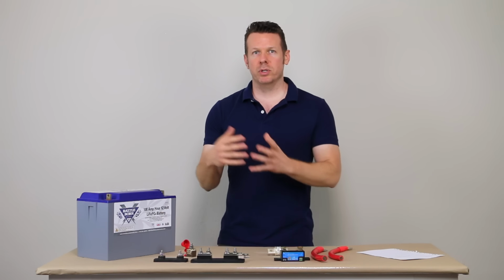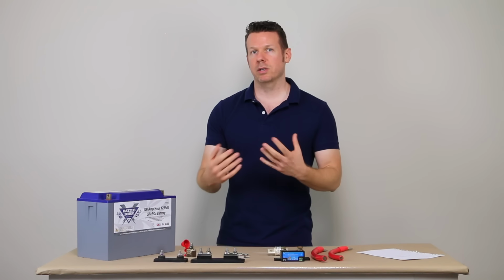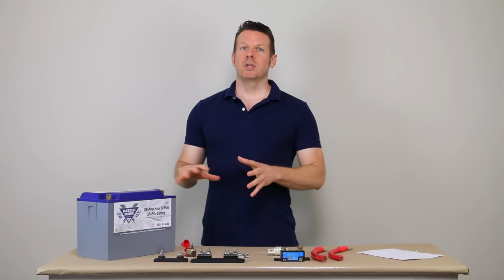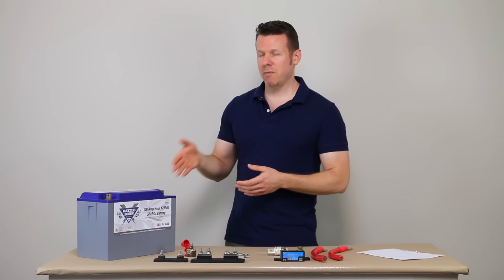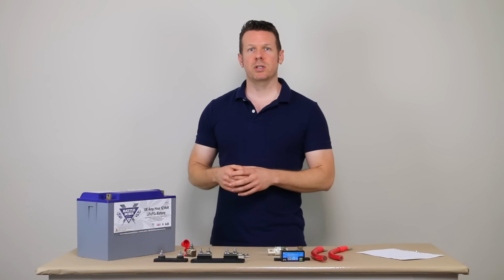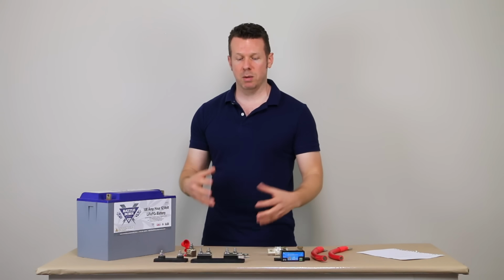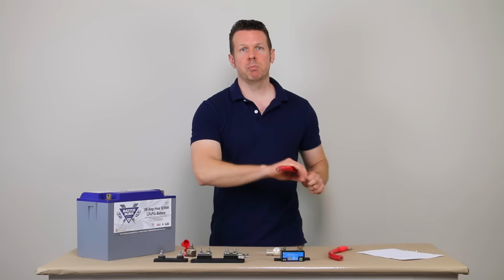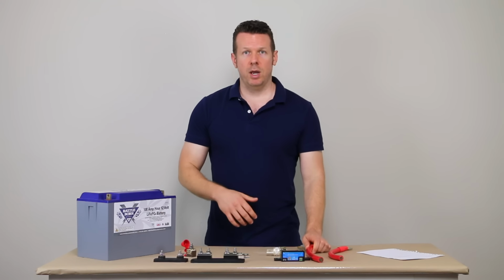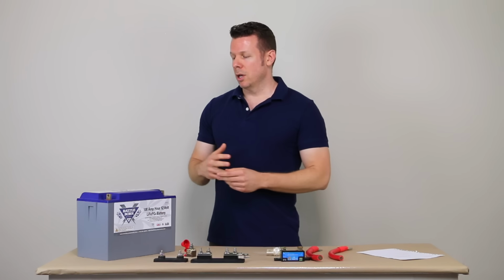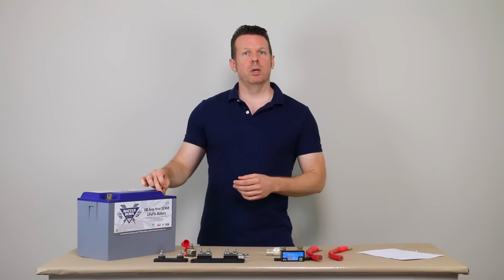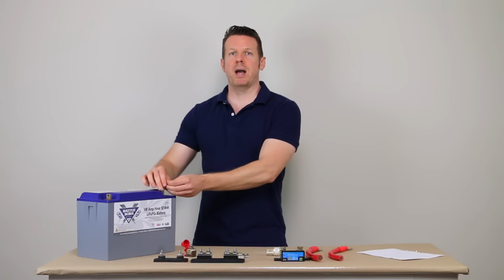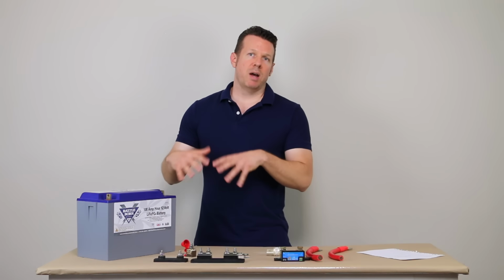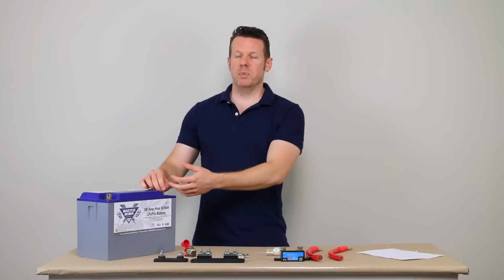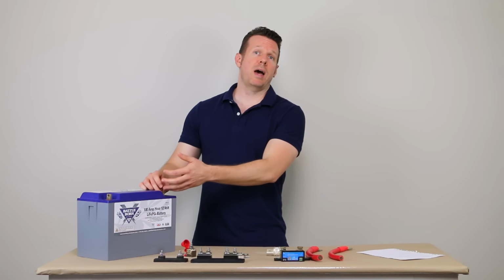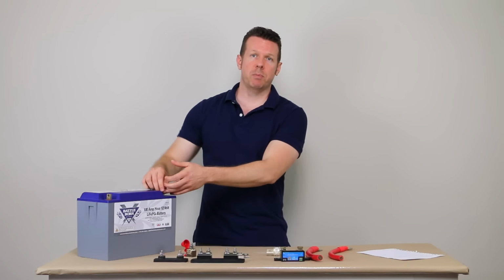Loose connections are going to be warmer than connections that are tight. So sometimes you can use your hand or an infrared thermometer. The hot parts of the system, usually there's some kind of problem, or maybe that component is too small for the current going through it, and it needs to be upsized. But in this case, it was a loose bolt on that main negative line coming back to the battery bank. We had some vibration back there, and there was not a locking washer on that bolt. Everything else had a lock washer. That particular bolt did not.